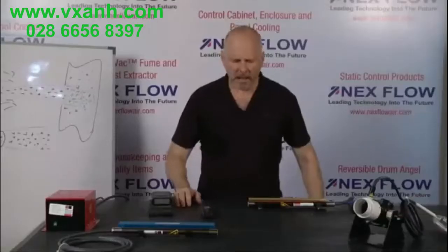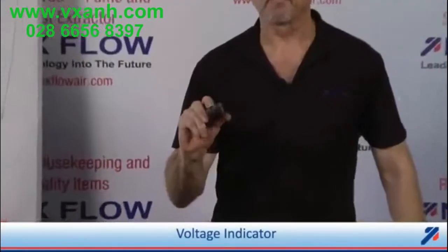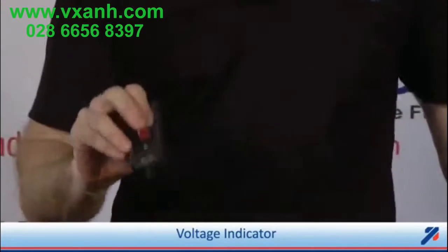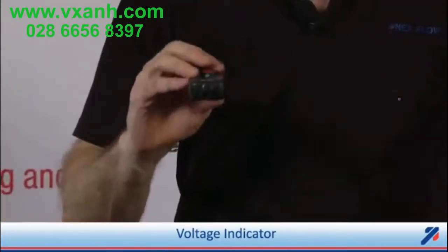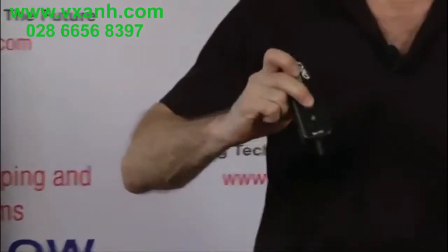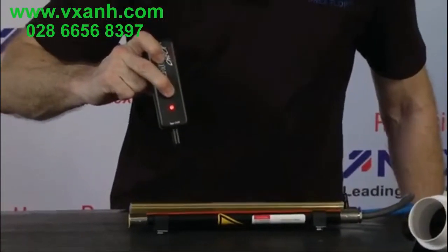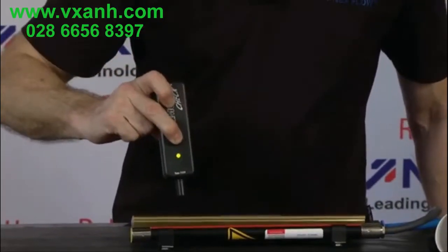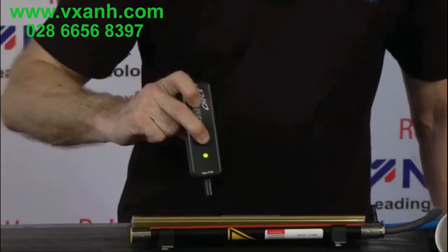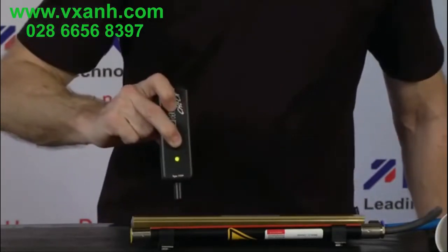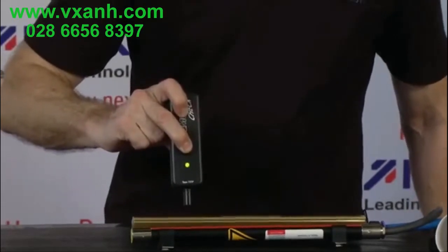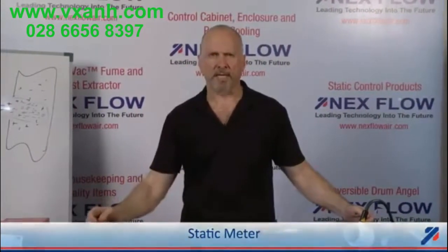We can do that. In order to be sure that your static devices are working, you should have 2 separate instruments. The first is a voltage testing device that will indicate that there's adequate voltage being created at the pins on the static device to produce the negative and positive ions that you need to remove the charge on the surface. So what you do is, with our device here, for example, when you get close to the static bar, it turns red, indicating that there is power going to the bar. When you get closer, it should turn green, which, as you can see, it does. That tells you that there's adequate voltage at the pins. There should always be about minimum 3,600 volts at the pins to be able to work properly. The second device that you need is the static meter, to measure the charge of the surface you want to remove the static charge from, before and after, to note that it is actually working.